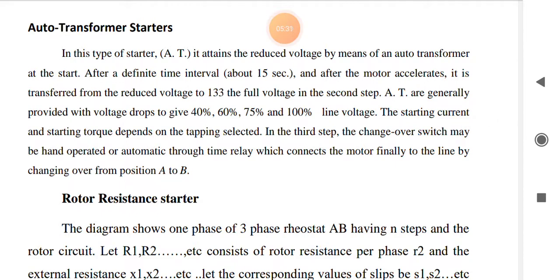Auto transformer starters. In this type of starter, the reduced voltage is attained by means of an auto transformer at the start. After a definite time interval, about 15 seconds, and after the motor accelerates, it is transferred from the reduced voltage to the full voltage at the second step. Taps are generally provided to give 40%, 60%, 75% and 100% line voltage. The starting current and starting torque depend upon the tapping selected. The changeover switch may be hand operated or automatic through a time relay, which connects the motor finally to the line by changing over the position from A to B.